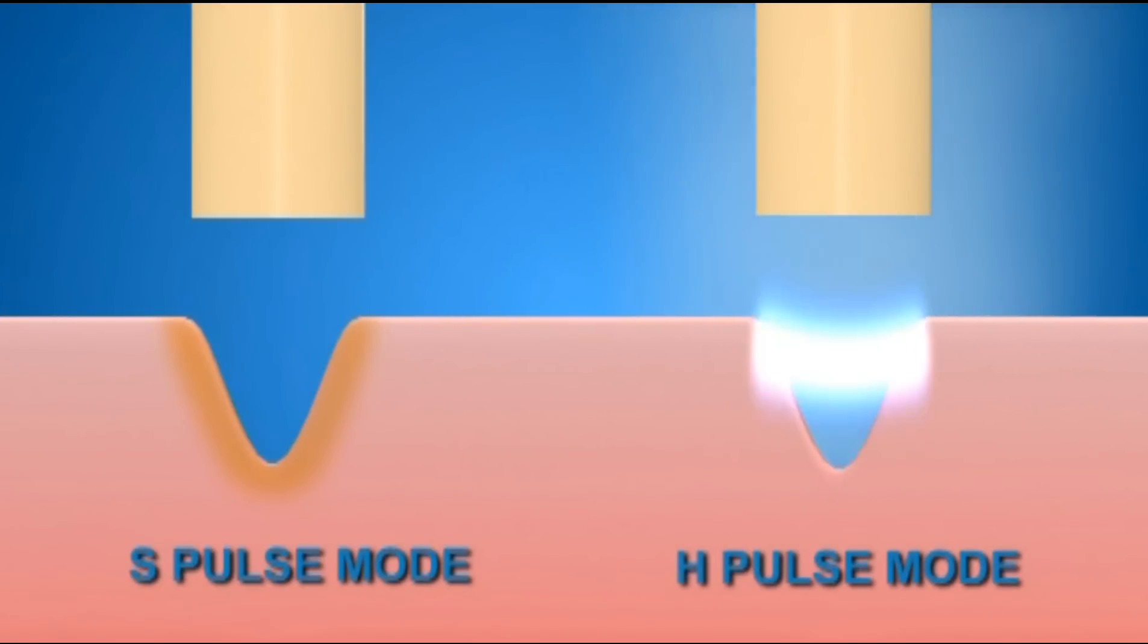Pulse mode has two settings: S, which coagulates deeper, and H, which cuts faster at the same power.